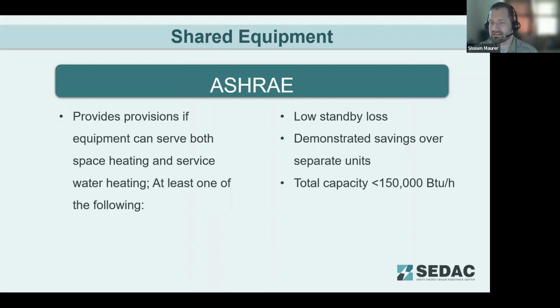So we commonly see this in heating systems that use boilers that may contain a domestic water generating coil that then exchanges heat with a nearby storage tank. Sometimes we see this with high-rise buildings with boiler systems. The primary reason to avoid bringing on the whole boiler to serve just the service water is that it doesn't match the load of that boiler, and so it's going to operate in a very inefficient way. By limiting the size of that system capacity, you're more likely to be closer to the design operating point of that boiler system when operating it for service water loads.